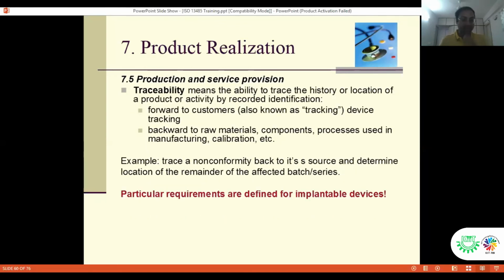The important thing over here is traceability. You have to prepare the batch manufacturing record starting from the purchasing activity till your dispatch. So that in case of any major adverse event, when you are going to have a product recall, with the help of a proper traceability matrix or traceability of your documents, you can recall your product from the market.